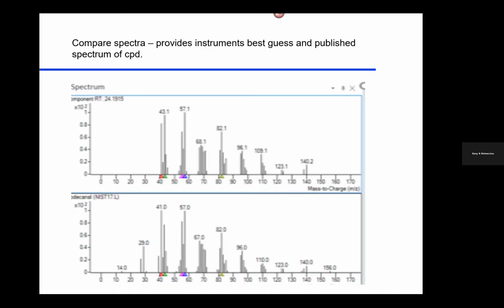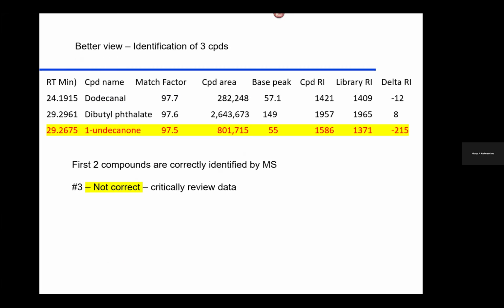And so, again, the person can go through this profile and say, yes, it looks good, or no, it doesn't. Out here, we've got a fairly decent sized mass up at 140 that isn't present to the same extent down here. It's close, but not quite. We got a 156 out here that doesn't show up there. So that's not a particularly good match. The idea is pay attention, check on your machine. The machine isn't necessarily flawless.